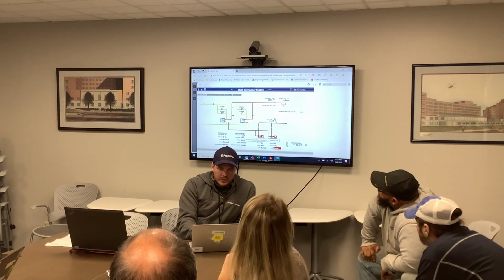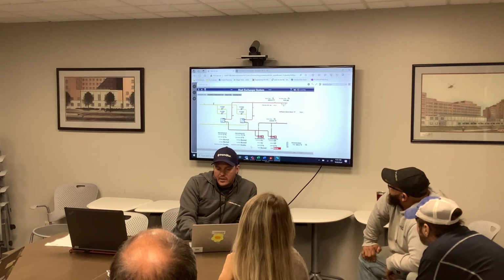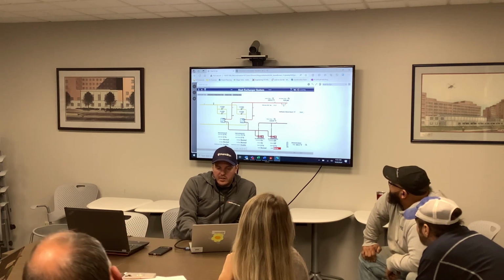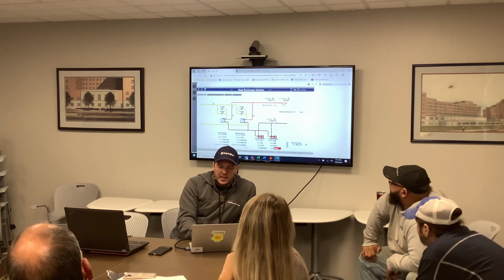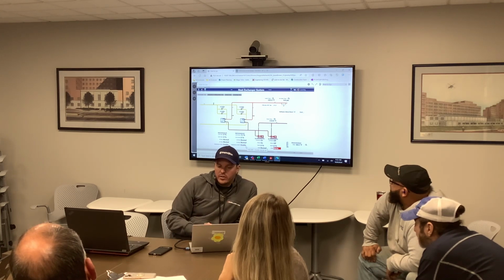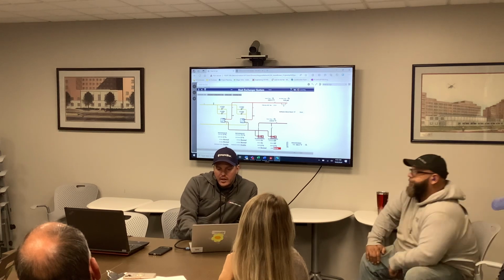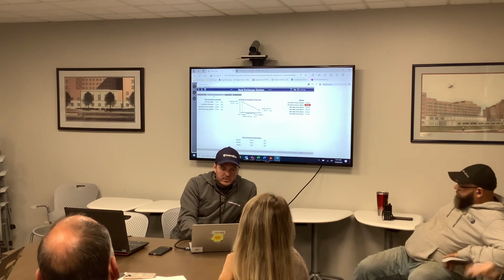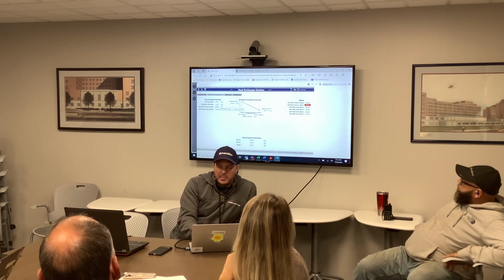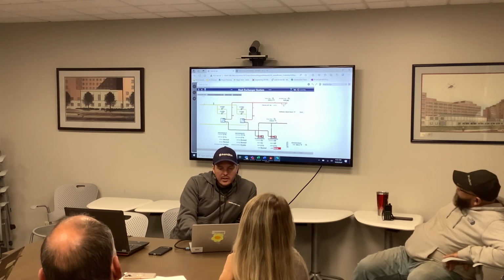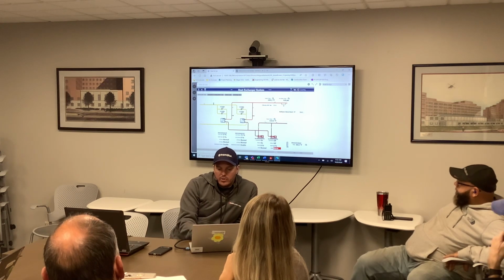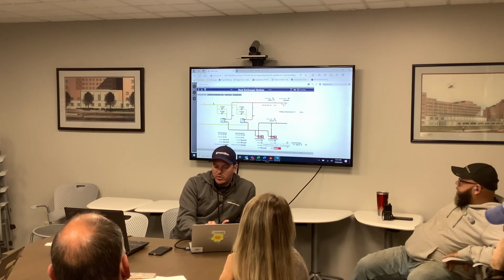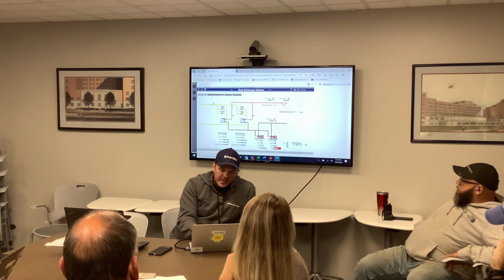You can see what the heat exchangers are doing down here. So you've got your one-third modulating up. You can see that the maintenance switch is enabled. That just means that heat exchanger, those two valves, are enabled. It's trying to maintain a hot water pressure of 1.5. That was set by the balancer. It is way over right now. This pump is in hand. I don't know exactly why it's in hand, but we're going to get to the bottom of that.